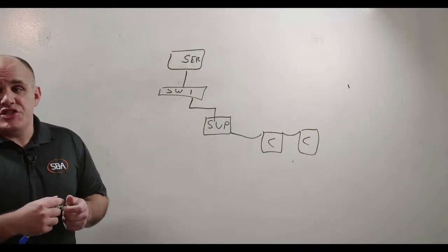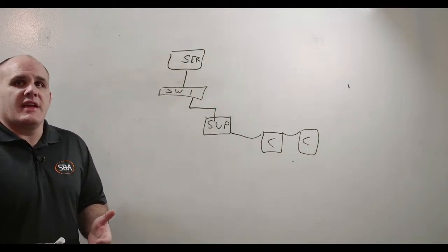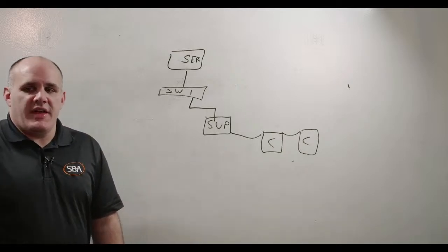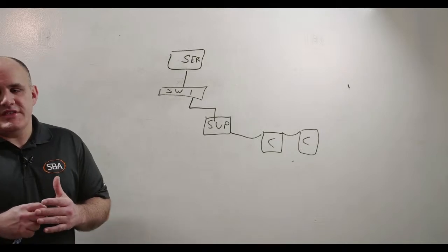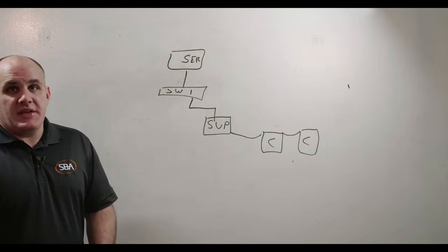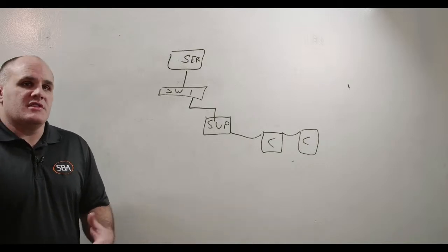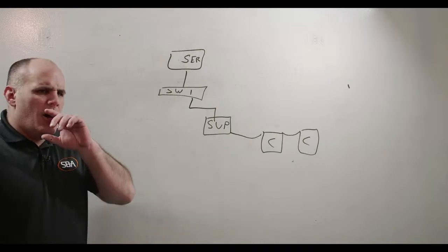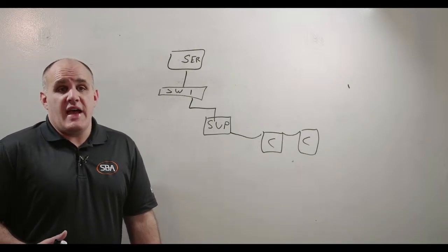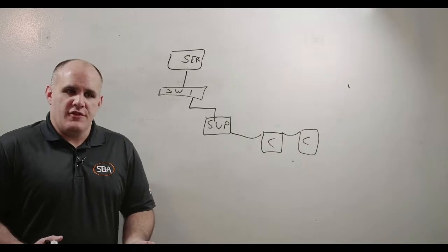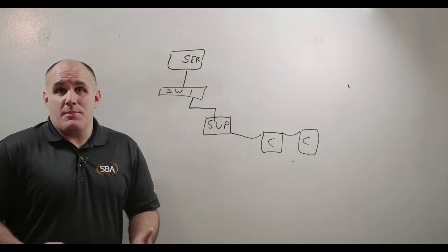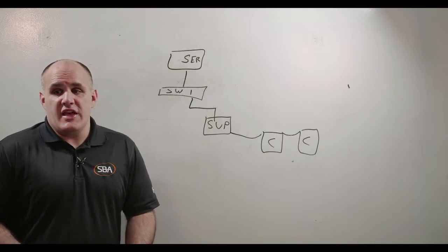So if you are engineering a system and you're looking at the system and you're like, okay, what parts and pieces do I put in which place? How I like to approach this is I start off by working on what are called application-specific controllers. So these are specific to applications. And these can be unitary controllers, or these can be actual VMA controllers, or they can be things like packaged unit controllers, things that you're going to integrate.